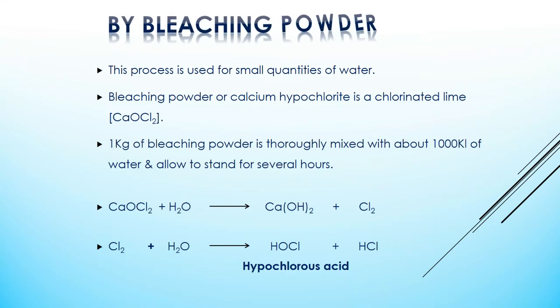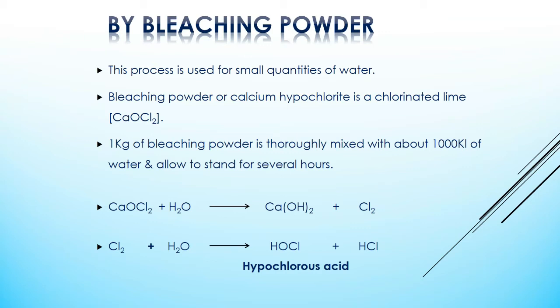Disinfection by adding bleaching powder. This method is used for small quantities of water. Bleaching powder is chemically calcium hypochlorite. In practice, about 1 kg of bleaching powder is thoroughly mixed with about 1000 kL of water and allowed to stand for several hours.